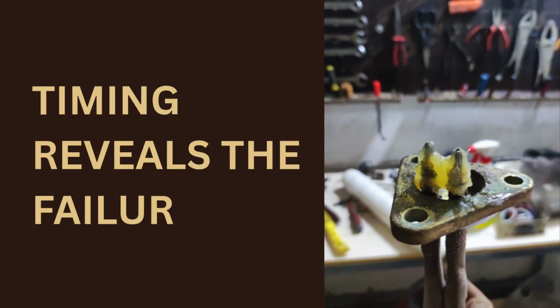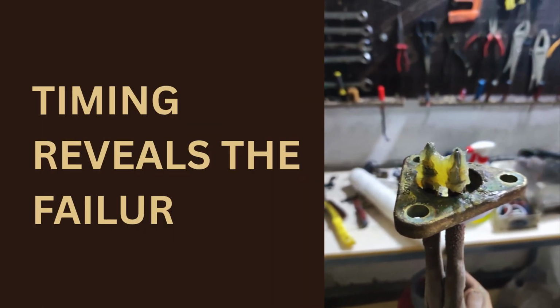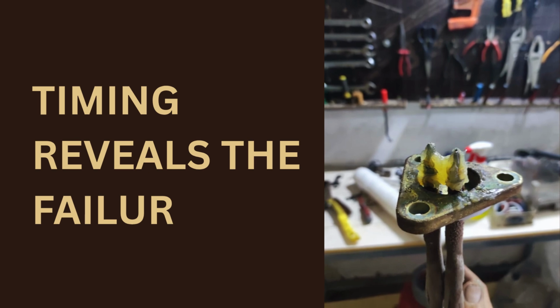A machine producing good steam initially but weakening gradually during operation tells technicians something extremely important. The issue may involve thermal recovery rather than immediate steam generation failure itself. Scale buildup, heating inefficiency, boiler stress, temperature regulation instability, or restricted steam pathways may all reduce long-term steam consistency. Technicians observe how the machine behaves over time instead of focusing only on the first symptom moment, because the timing of failure often reveals the nature of the problem underneath.